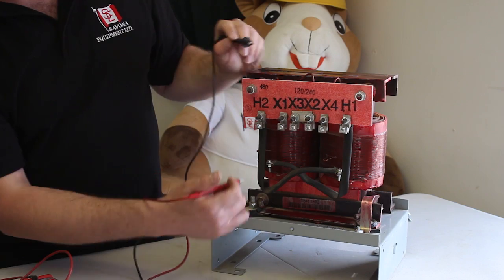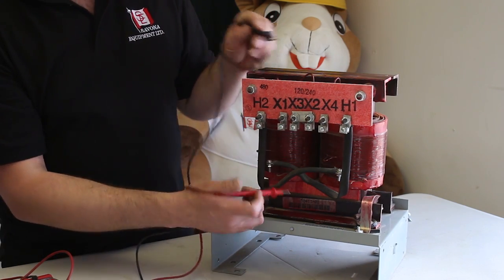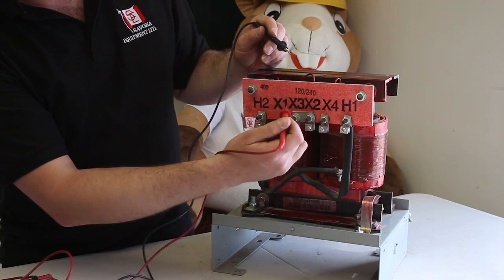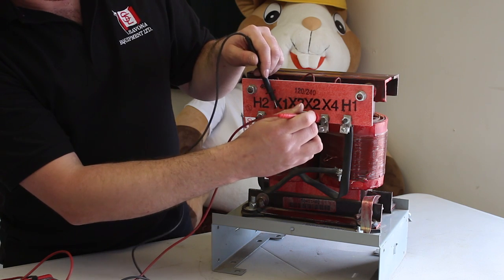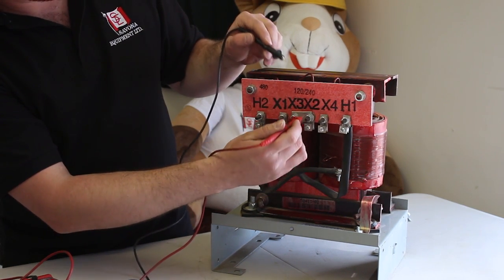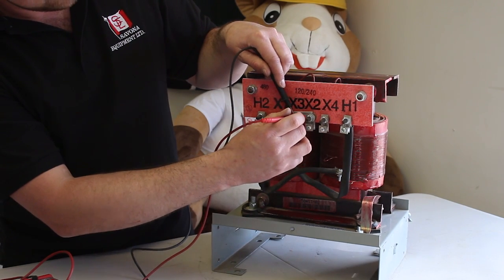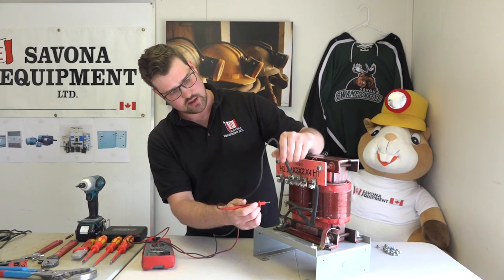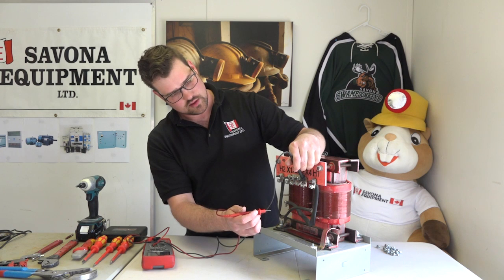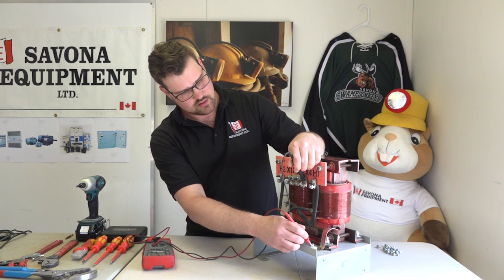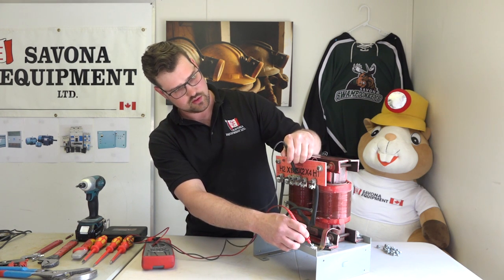And next we'll check the secondary windings. So I'll go X1 to X4. We got continuity. And then I'll go X3 to X2. Okay, and then I'll check each winding to ground, and there should be no continuity.